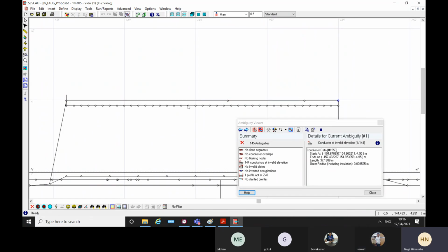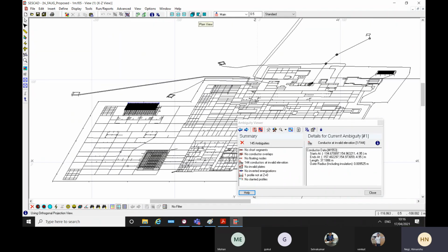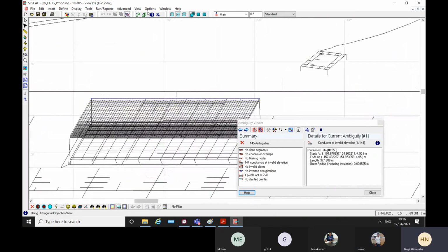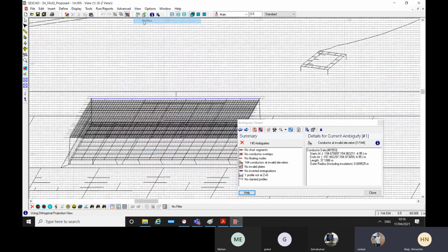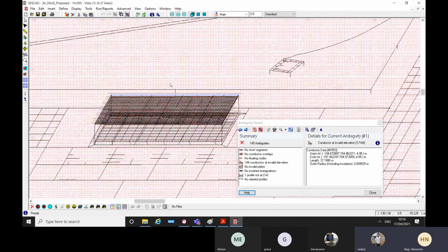Some manufacturers say that if you are a first floor GIS, this copper mat should be below this, right here on the ceiling, like your ceiling fan. Ceiling, I got it. So it should be stuck right to this floor. Then in that case I will model this down, and to calculate any voltages here, we calculate one imaginary surface, called profile points, and then I can calculate the voltages.